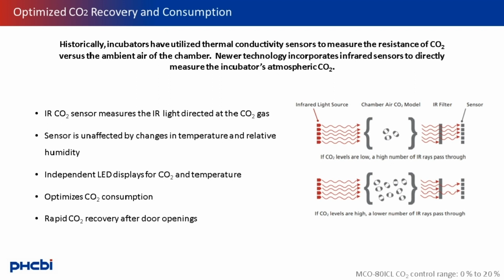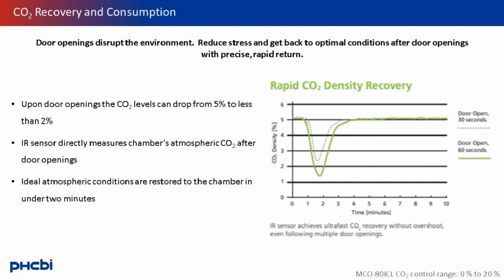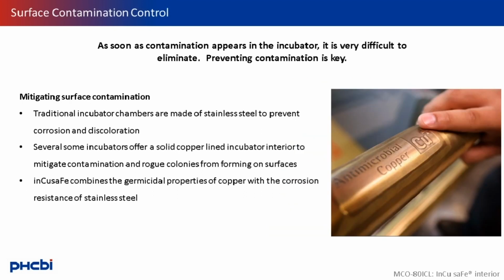And as we have mentioned before, door openings can cause big changes in an incubator's internal environment. This allows the right amount of CO2 to be quickly delivered to the incubator chamber, restoring the proper CO2 levels without any overshoot. An IR sensor enables the incubator to rapidly recover that CO2 level after the door opens. When the incubator door is open, the CO2 density inside the chamber can drop around 3%. In 2 minutes, the IR sensor brings CO2 levels back up to the ideal atmospheric conditions. And again, door openings can pose many threats to the internal cell incubator environment.